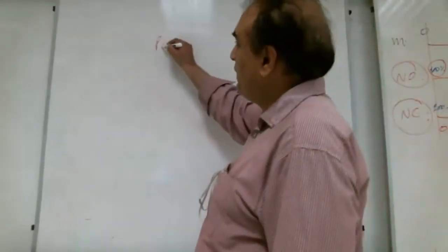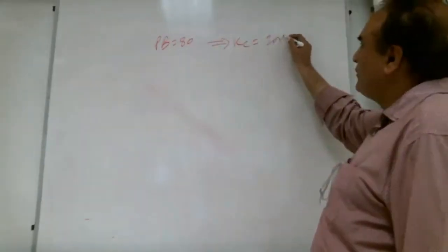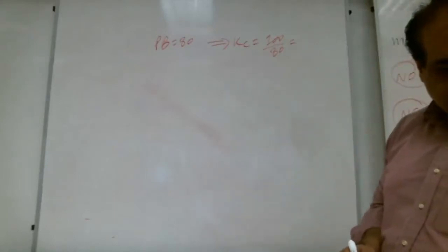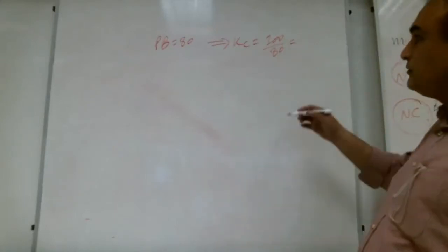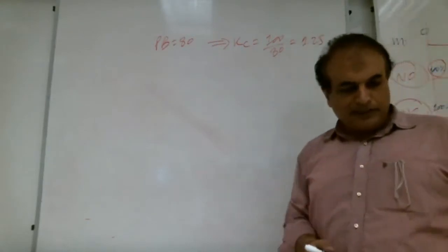Now you please read the second question. A proportional controller has a proportional band of 80. What is the proportional gain? Yes, Shabab, how much is the gain? 100 over 80, how much? Yes, brother, how much? 1.25. A lot of brothers are typing. Very good. Yes, brother, please continue.